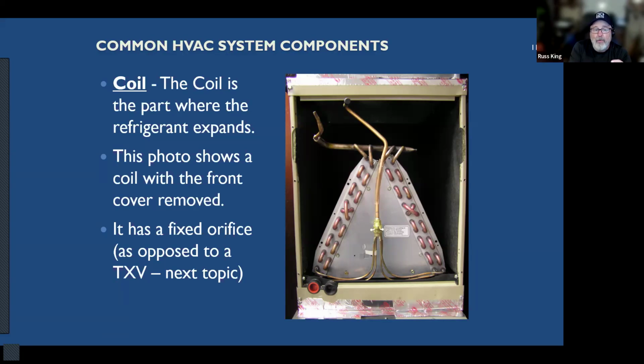All right. If you've ever used a Coleman stove or a Coleman lantern, or if you've ever used one of those spray cans to spray air to get the dust out of your keyboard, and you notice that the can gets cold, it's because there's a liquid turning into a gas. It's the same principle. So this compressed liquid expands into a gas and gets really, really cold. And that happens inside this thing. If you look on the side, this kind of looks like a radiator in the front of your car. It's got a bunch of aluminum fins in it. Okay. And these tubes have the really cold gas running through this radiator, and the air blows through there and it cools the air. Okay. And so we call that the coil.